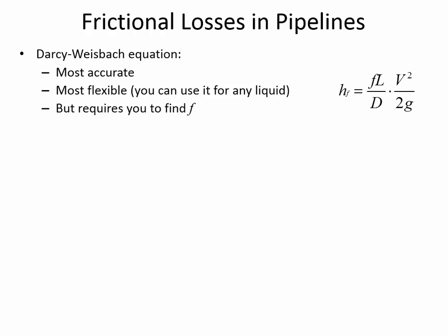And you are given the option, for example, in the program Water Gems. You remember in Water Gems that one of the first things I had you do was switch it away from the Hazen Williams equation and switch it into Darcy-Weisbach. And the reason why Darcy-Weisbach is superior is that it's, number one, applicable for any liquid, not just water, whereas the other equations that we have as options are based only on water.